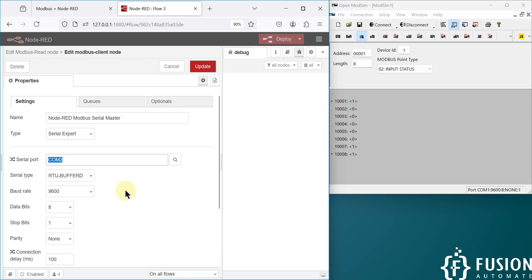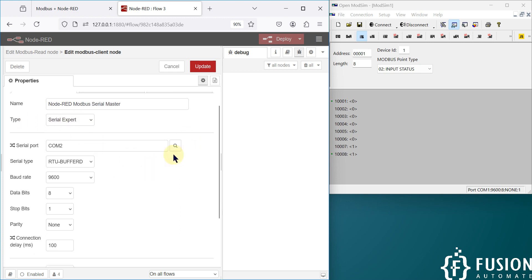The connection parameters: COM2 port, serial type is RTU, baud rate is 9600, data bits 8, stop bit 1, and parity none. Everything is the same as in the last three videos, and the type is serial expert.